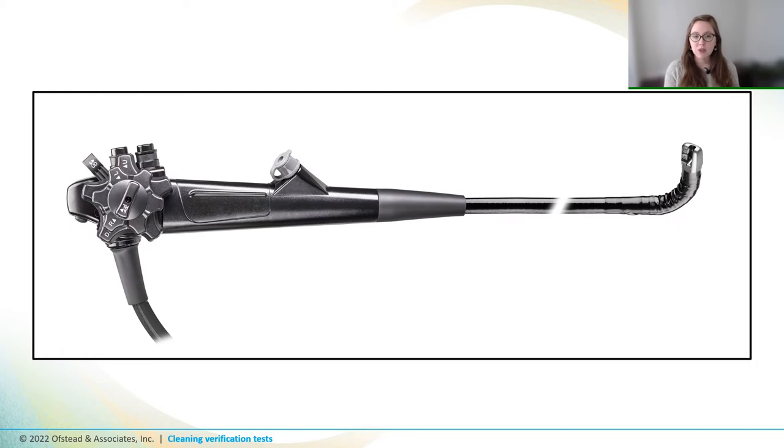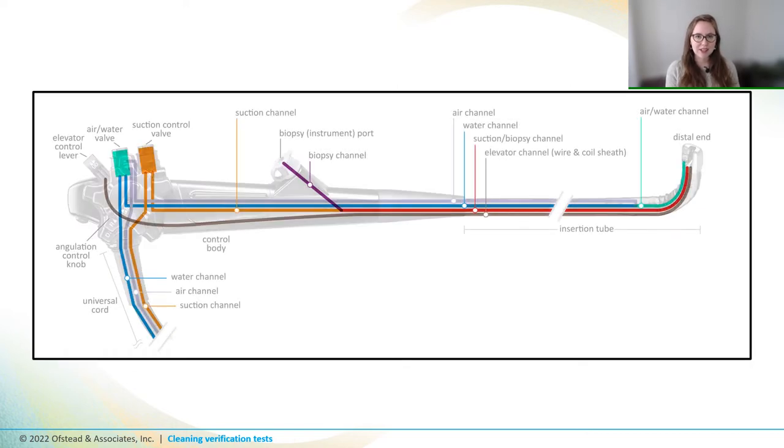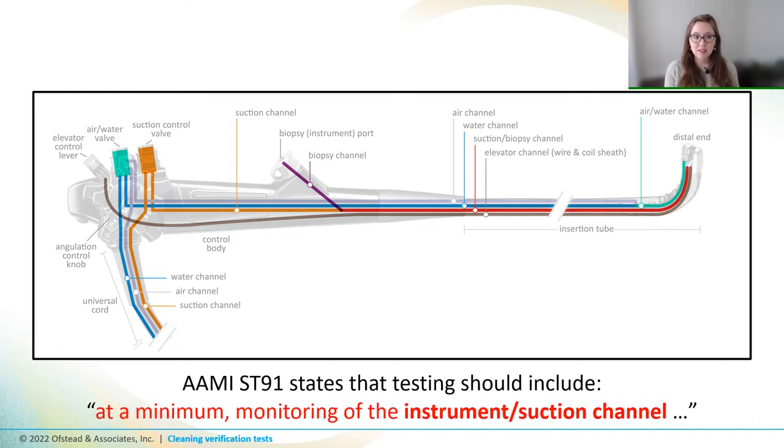So now we know of a few different kinds of tests we can do, but what are we testing? Endoscopes kind of look like big garden hoses on the outside, but they're pretty complicated on the inside. And the new AAMI ST91 standard says that testing should include, at a minimum, monitoring of that big instrument suction channel, which means you've got to figure out how to take samples from inside your scopes.